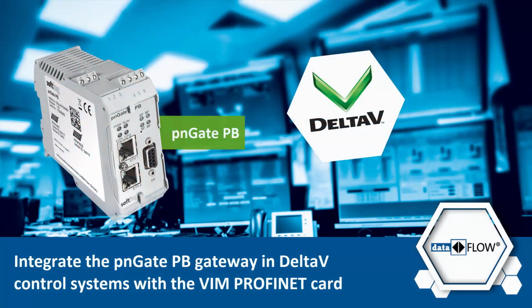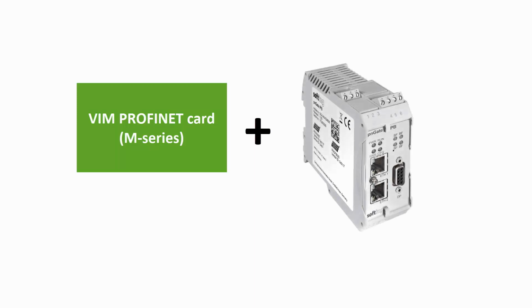In this tutorial, you will see how to integrate the pnGate PB gateway in DeltaV control systems via the VIM-2 Card PROFINET. As a first step, you need to configure your VIM PROFINET card M-Series and the pnGate PB. Connect your VIM card to the DeltaV DCS, first RJ45 port on the front, and the VIM card to your workstation, second RJ45 port on the back, and the pnGate PB.